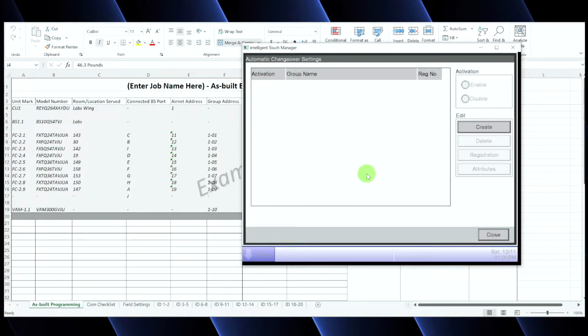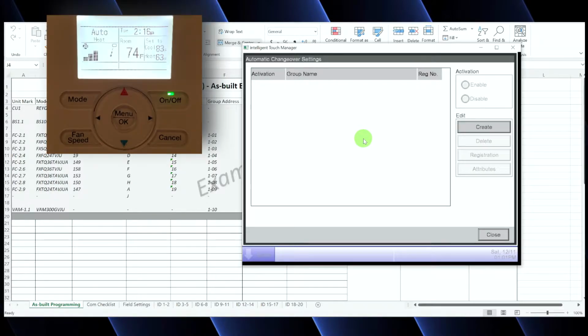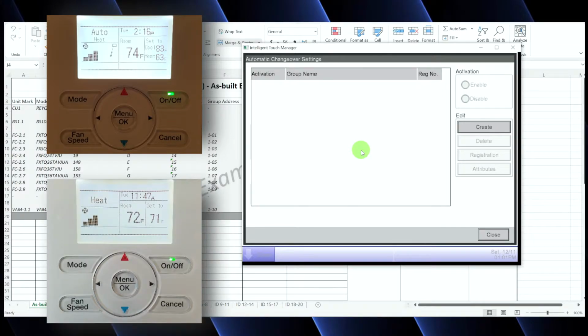Now here's where you're going to set up the actual auto changeover for all your zones. You see, before you hooked up the ITM and registered all the addresses, all the stats were operating independently as if they were just a one-to-one mini split or VRF system. They had auto on the thermostat. They could do whatever they wanted, heat, cool, to their heart's desire. But as soon as you hooked up the ITM and registered the group address to the ITM, the ITM takes control of the auto mode. And now if you walk over to the thermostat, you're going to notice there's no more auto mode. It's because the ITM handles auto and scheduling.